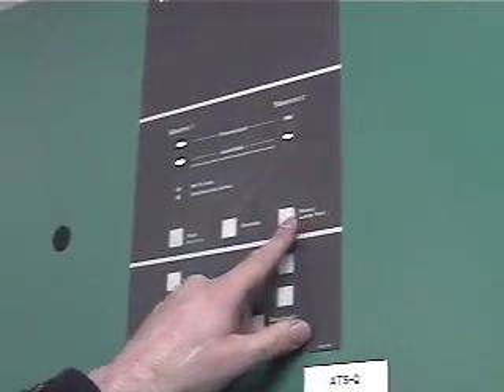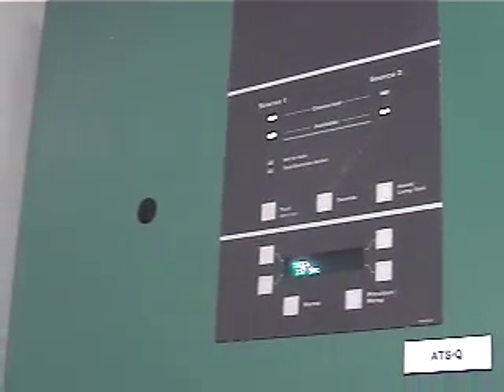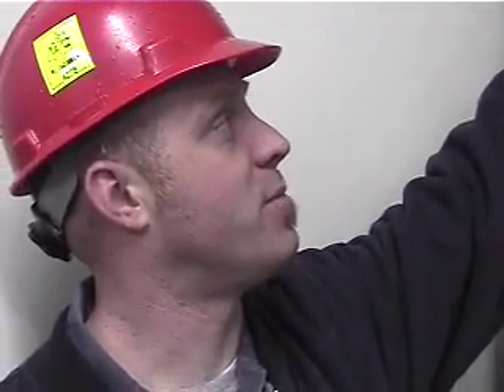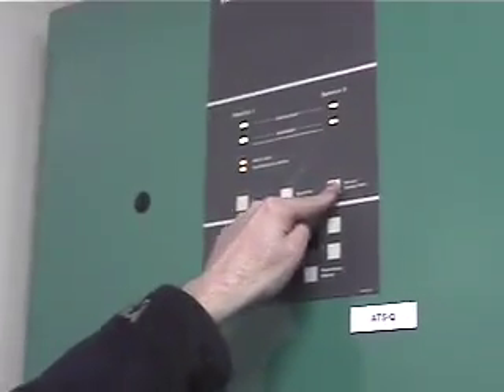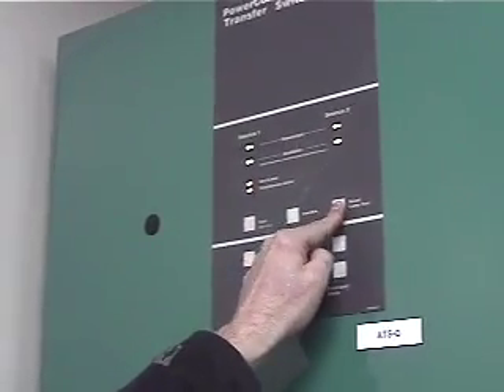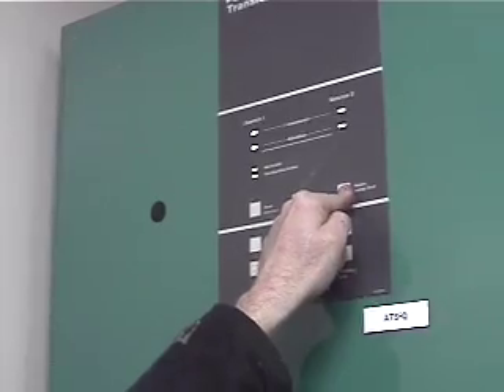Reset or lamp test. If you ever have a problem and the transfer switch binds up or something goes wrong, it's going to come up there and say you have a problem, and you can reset it here with the reset. If I push it and hold it in, it's just like our control out on the generator - it checks the LEDs to make sure they work.